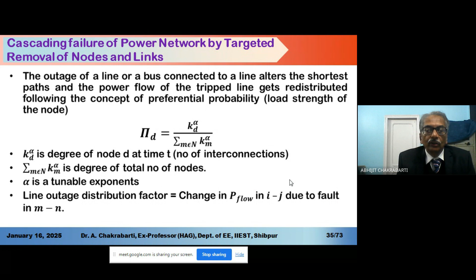Now we have done a simulation for the 57-bus system. I have told you earlier that line number 79 is the line of highest betweenness. So when line number 79 is tripped, the betweenness is distributed to adjacent lines. You see 10, 11, 13, 15, 25. This is the maximum power capability that could be achieved, and this is the power that is available. You see that the maximum power possible for line number 11 is, say, 20 megawatt. So 20 megawatt is surpassed here. In other cases, all these values are less than the maximum power. So in this case, this line will obviously trip. So line 11 is tripped.